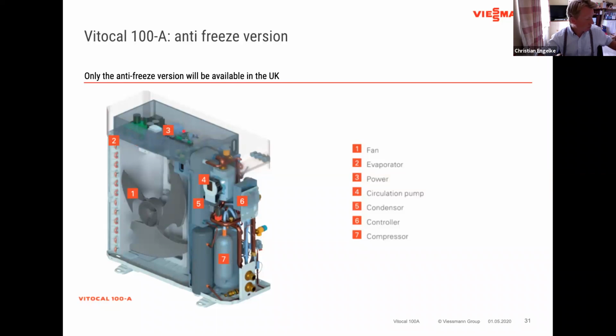Number three is the control board. That's where the electrician is connecting all the cables to it. They're coming in from the back. And then on the right hand side, we have the rotary twin compressor located in here, all the refrigerant pipes and water pipes from the condenser. The condenser is here, number five, a pre-insulated plate heat exchanger.